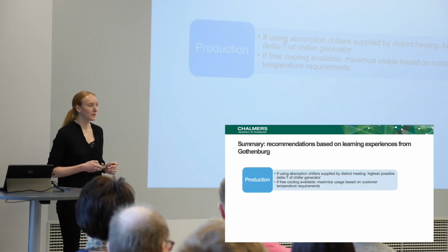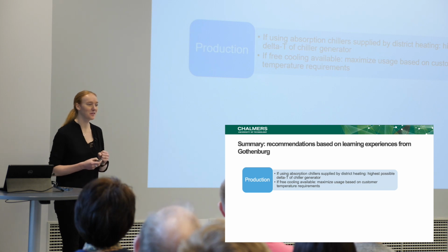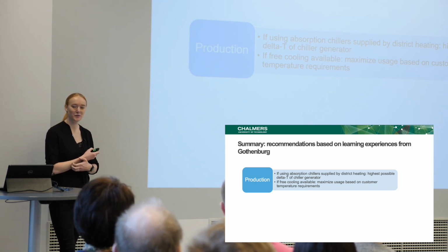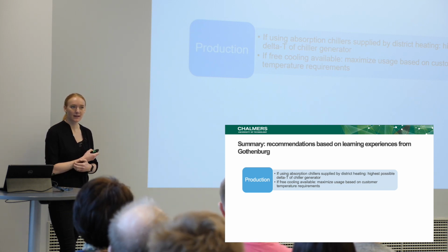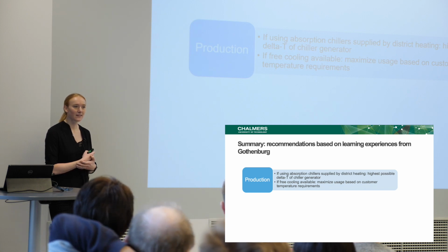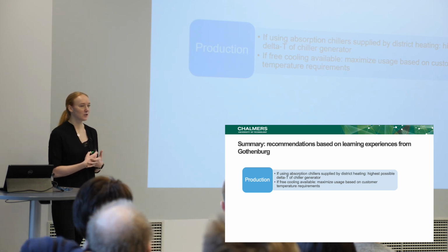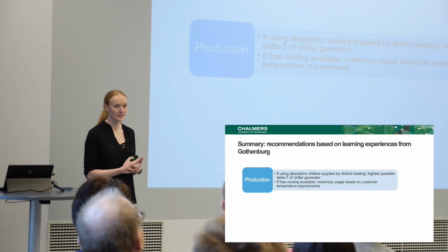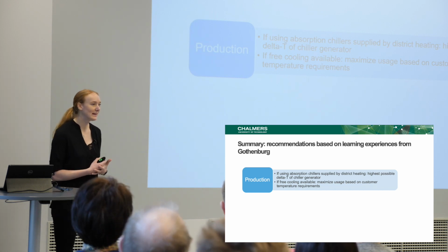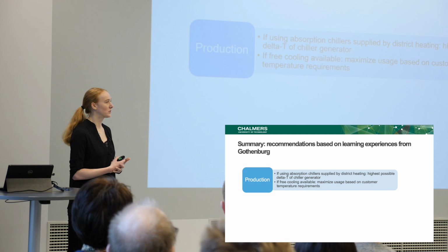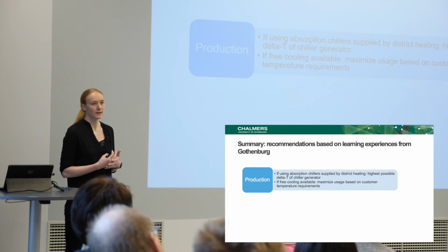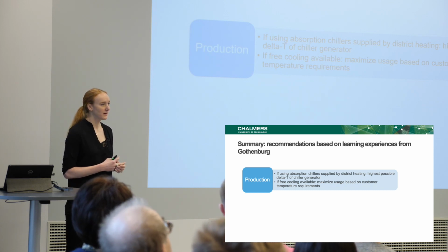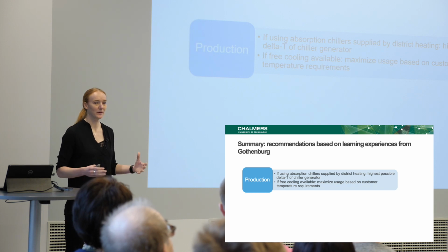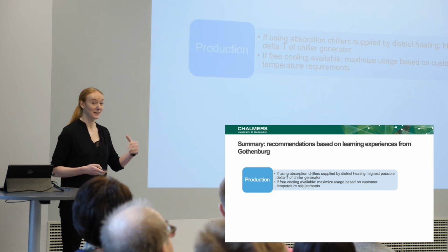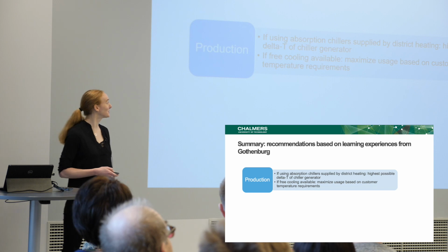And to summarize all the learning experiences from Gothenburg, one main point is that if you have the ability to use absorption chillers based on waste heat or district heating water, then you want to make sure you have the highest possible delta T in the chiller generator, so you don't get problems with delta T on the district heating side too. It's enough with the cooling side.